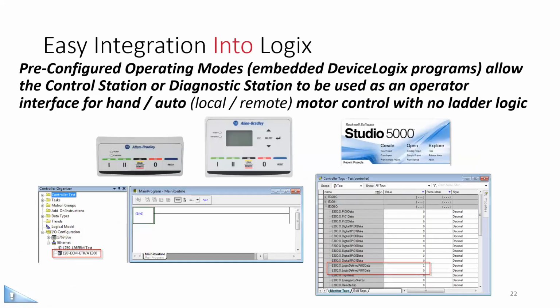The control station and diagnostic station are operator interface devices. They provide buttons for start, stop, control, and reset commands. The buttons and corresponding LEDs are controlled via the user selectable operating mode, which is embedded in the DeviceLogix program. The operating mode requires no additional ladder logic in a Logix controller. So you just simply add the E300 to the Logix project, select the appropriate operating mode, and use the output tags, they're in this red box down here, to control the motor remotely with the Logix controller.